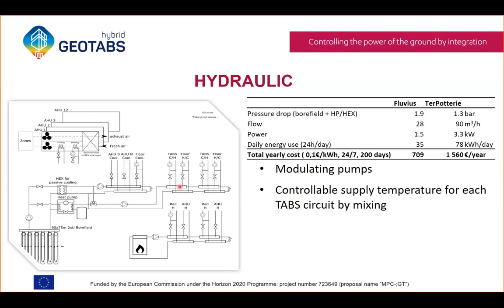You can go even further by also including two-way valves for the sub-circuits, such that, for example, you can close the circuit of the middle floor of a building as that floor doesn't need any more heat, while the ground floor or the last floor stays open. So in general, try to control the different TABS circuits as well as possible, because MPC will really make use of that.